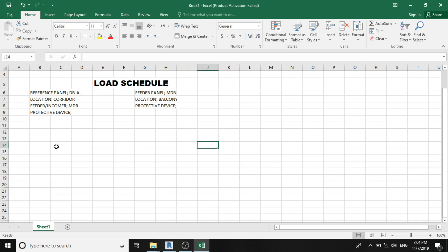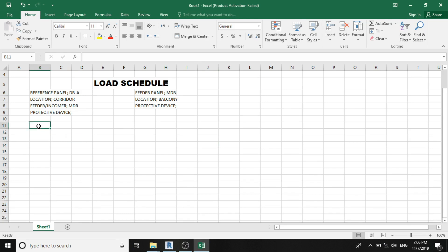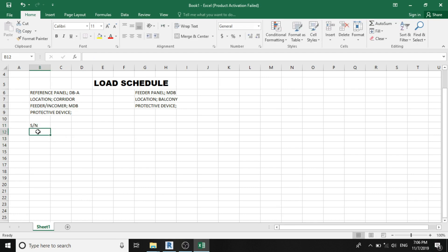Now let's proceed to the load schedule table. The first column we'll be having for our schedule table is the slot number, or you can call it the serial number, or you call it the circuit number. So let's code it to be S/N slot number. And for electrical distribution panels, they are being grouped in three phases, which implies a single way panel will have three phase or three slots, while a double way or a two way panel will have six, three way we have nine, and four way we have twelve. So let's assume for this computation, we are using a four way distribution panel, which implies we'll be having twelve slots.